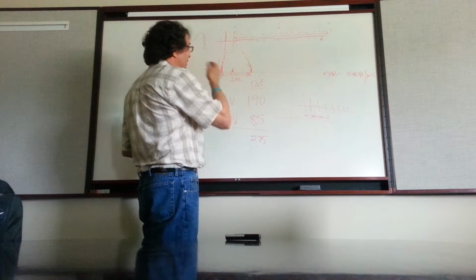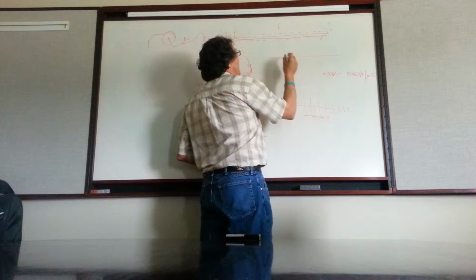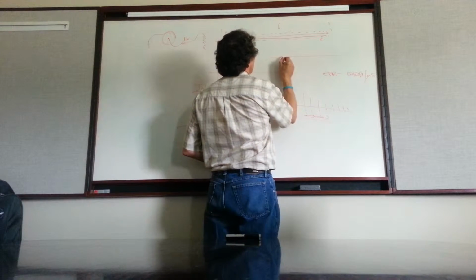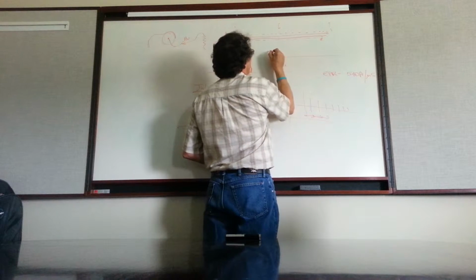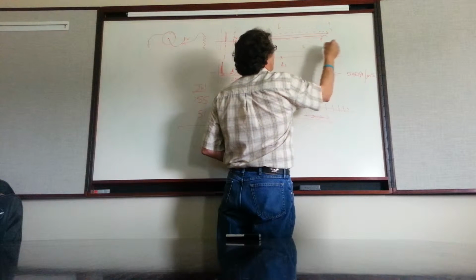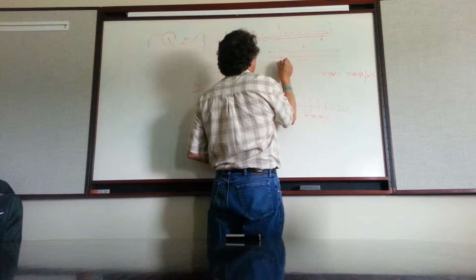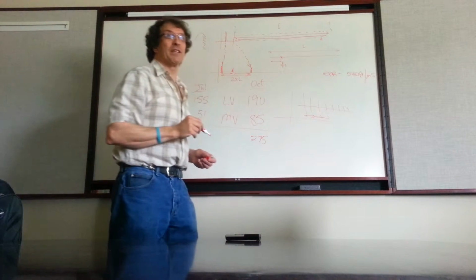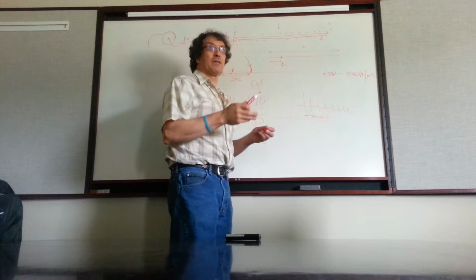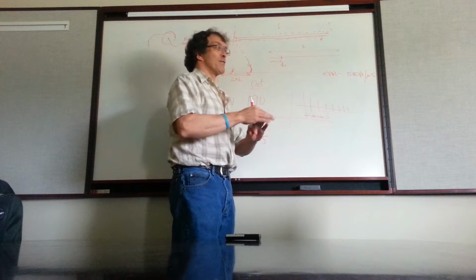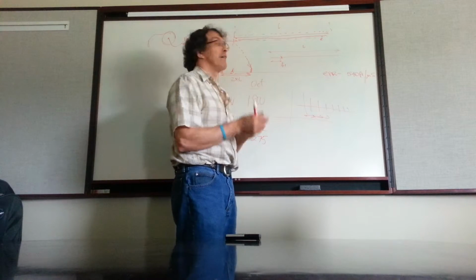What actually happens, if you look at it as a simple graphical way of doing it, is, let's say my fault is 1/4 of the length. And this is L. The fault is 1/4 L in. So that's where the fault is. So I get pulses from the fault, because that's what you do when you do fault locating. You've turned off your calibrator, and you're looking at pulses that exist at the fault area.